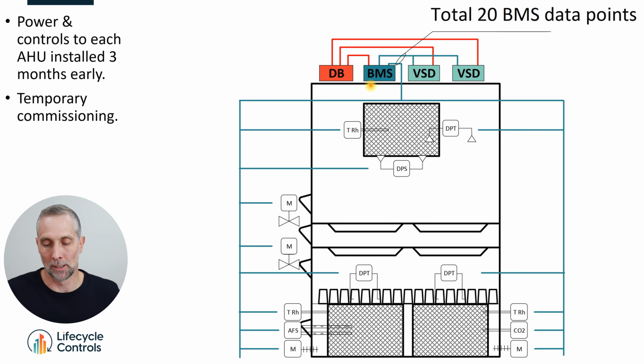even if you just used a little, one of those small UPSs, those small ones you get, like portable UPS. You just put in your trolley, you power it up overnight, and now you got a UPS power supply to power up your 24 volts transformer to power up this panel. You don't even need to have a mains temporary power supply. Just have a big UPS. Have 10 UPSs on site, power them up overnight, and the commissioning techs carry them around with them and deplete them and get a new one after lunch.